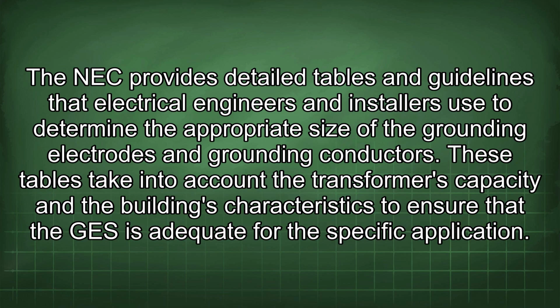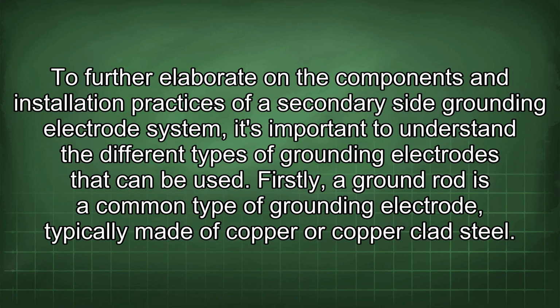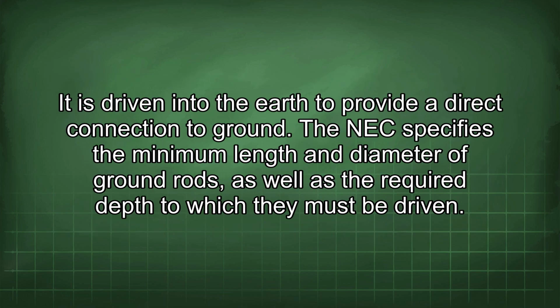the specific application. To further elaborate on the components and installation practices of a secondary side grounding electrode system, it's important to understand the different types of grounding electrodes that can be used. Firstly, a ground rod is a common type of grounding electrode, typically made of copper or copper-clad steel. It is driven into the earth to provide a direct connection to ground.